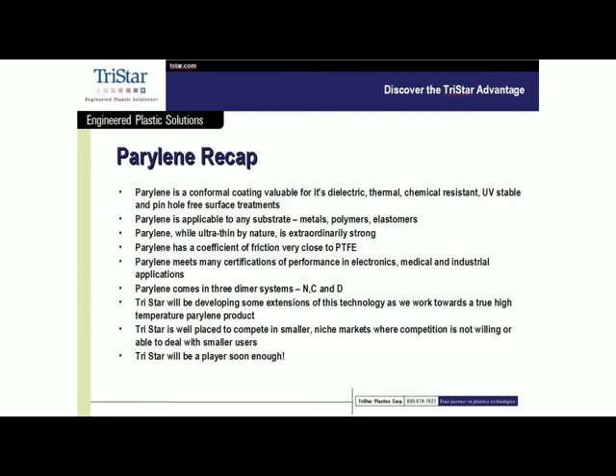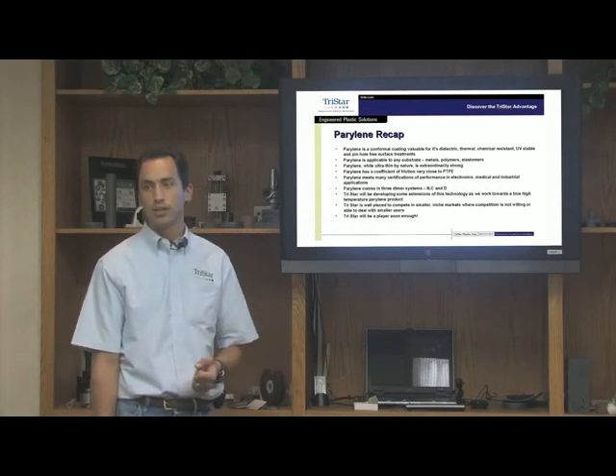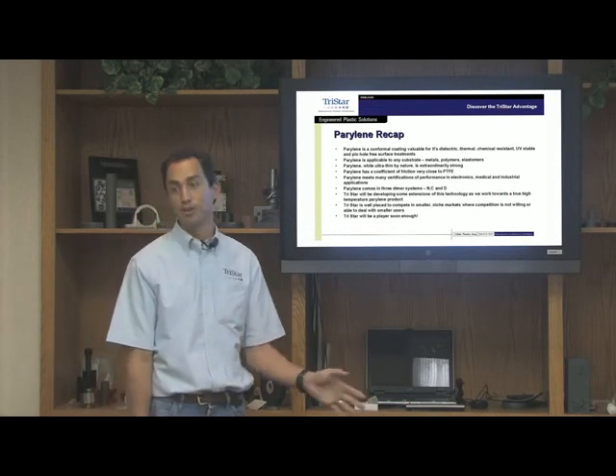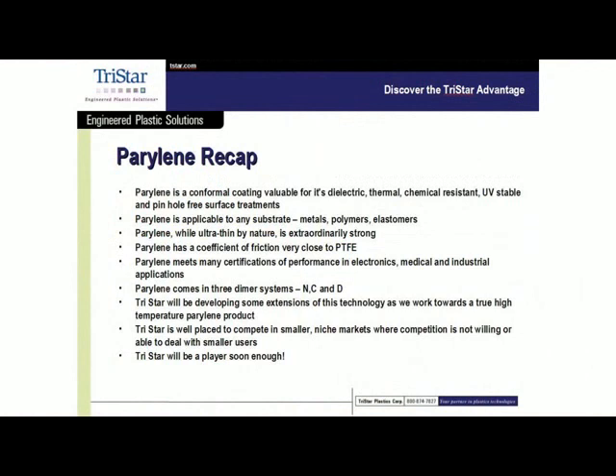For most applications, parylene is used to protect and to lubricate materials. Protection is the primary objective — protecting glass, protecting circuitry, protecting metal, making cheap polymer resistant to solvents, and providing lubrication. Especially with small devices, they can't afford any contamination. If a material is emitting contaminants, coat it with parylene. If an elastomer is in actuating motion and needs a lubricant, use parylene — you won't have any loose contaminants. Because it is fully conformal, you can have very thin coatings and still get barrier protection and lubrication — quarter mil thick coatings are quite satisfactory.